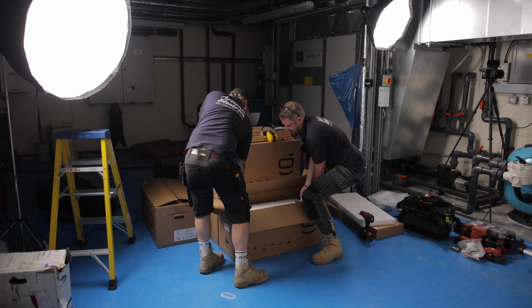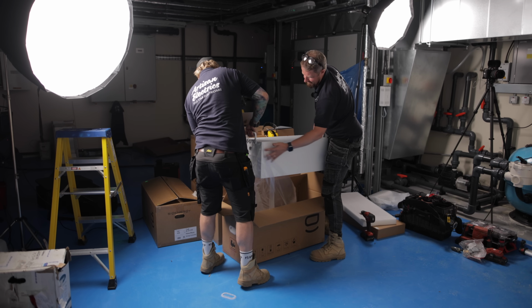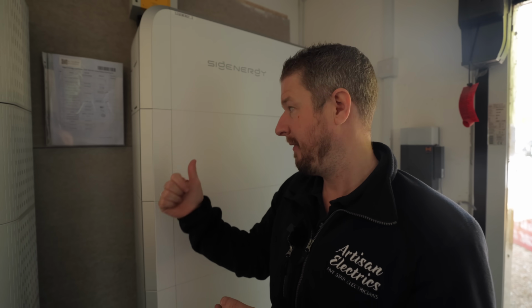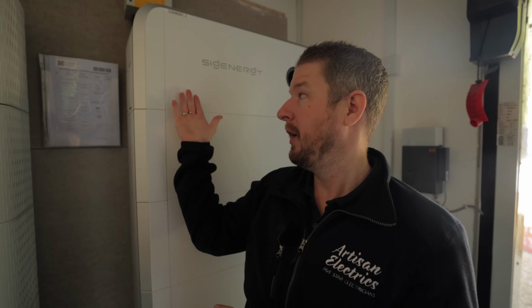Now, there's one other really important thing to factor in when installing a battery storage system, and that is that each battery module has its own maximum charge and discharge rate as well. So these 8 kilowatt hour modules have a maximum charge and discharge rate of 4 kilowatt or 0.5 C. What that means is that if you only fitted one battery module with a 15 kilowatt inverter, it would still only be able to charge and discharge at 4 kilowatt. It's not going to charge and discharge at 8. So if you've got a maximum charge rate that you need to achieve, then you're going to need to install enough battery modules to meet that maximum charge rate.